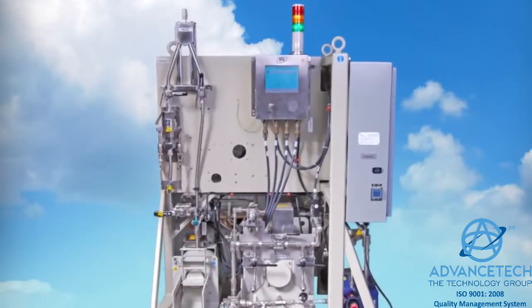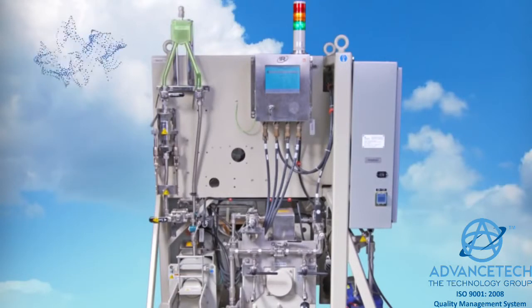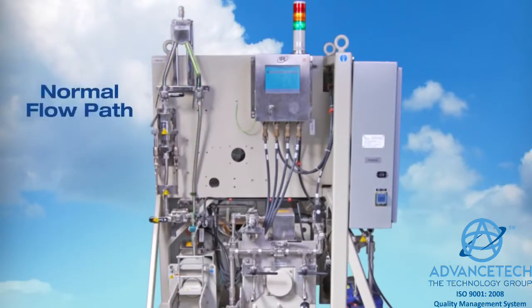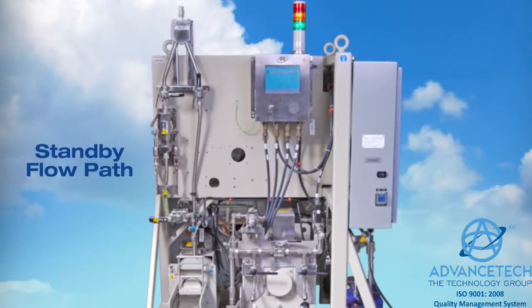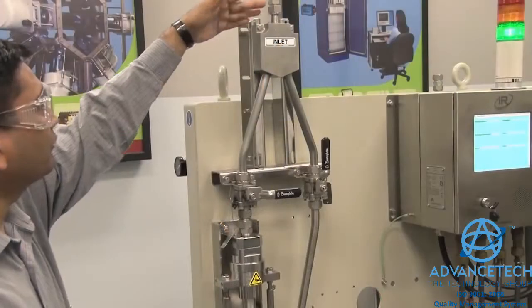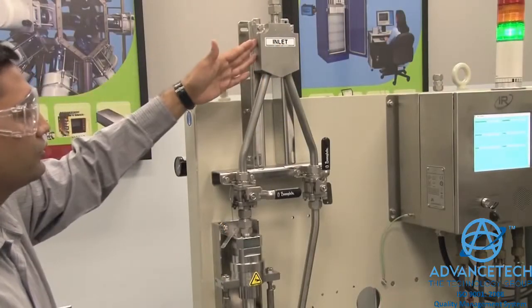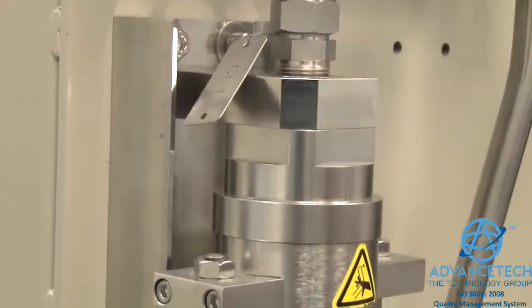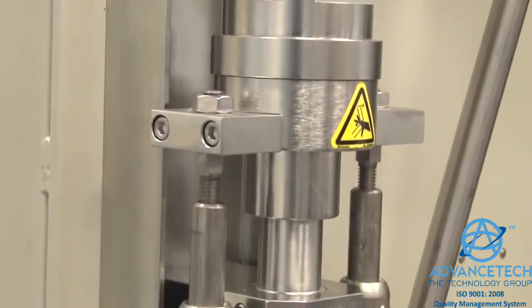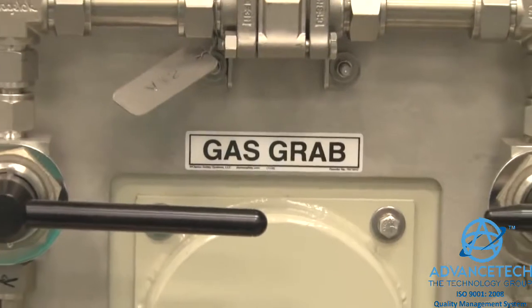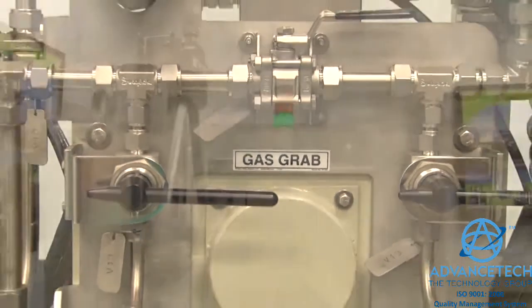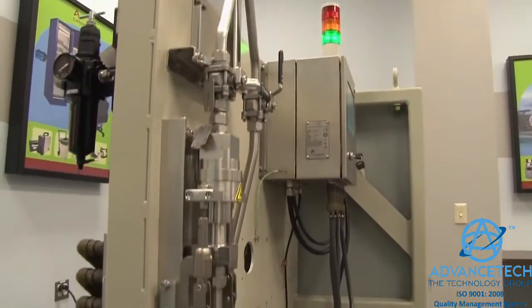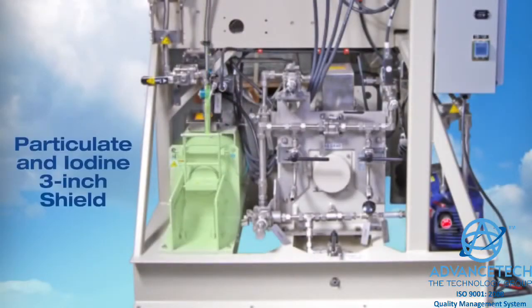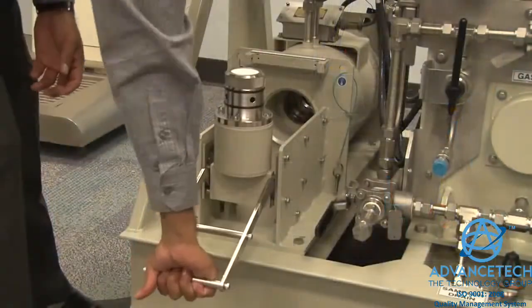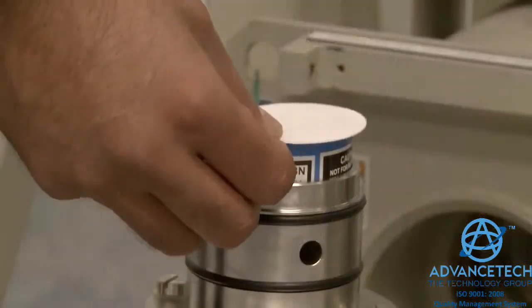The sample flow being monitored first comes through the flow splitter, which divides the sample into a normal flow path and a standby flow path. The flow splitter is designed per ANSI N13.1 to reduce particulate loss and improve collection efficiency at the filter. All of the tubing along the sample path is stainless steel. No hoses are employed. Normally, the flow goes straight to a 3-inch shield which surrounds a detector in front of the filter paper and charcoal cartridge.